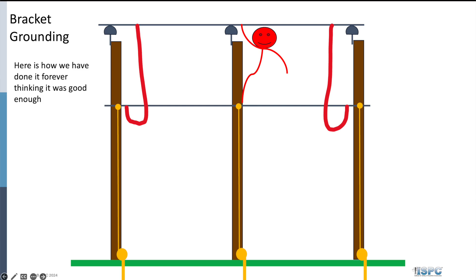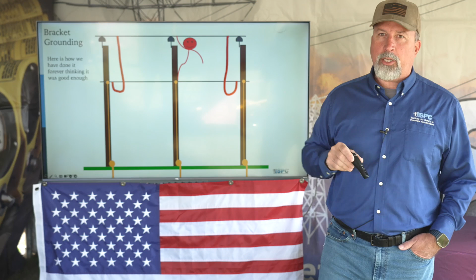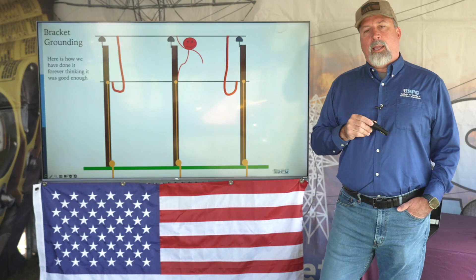We realized, as one of our safety principles states, current flows in every available path. So here you have a guy working on the center pole, with bracket grounds installed on either side of the worker. But whether it's induction or a fault, voltage and current are going to flow in both your conductor and your neutral, through your bracket grounds, and depending what the worker is touching, through them as well, and then through your grounds to ground. So you're going to have current flowing everywhere in this configuration.